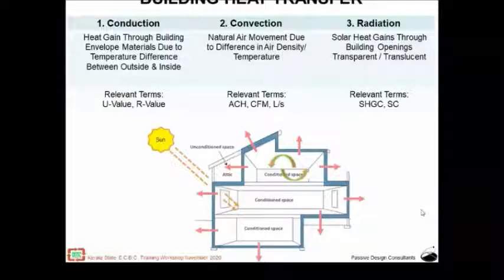Looking at convection, we all know that buildings need fresh air, buildings need ventilation. When we are designing a building for ventilation, the air outside, since it is hot, will come in and heat up the indoor environment. Even if we are doing mechanical ventilation with air conditioning, the air conditioning also requires that fresh air is supplied to maintain indoor air quality. Therefore, the hot outside air that we are bringing in needs to be treated in order to reduce the heat gain.